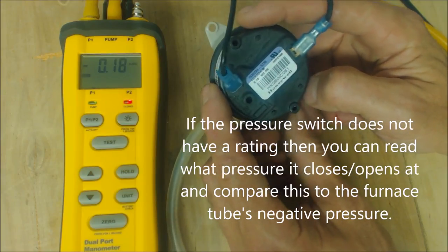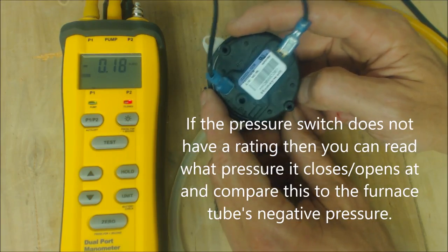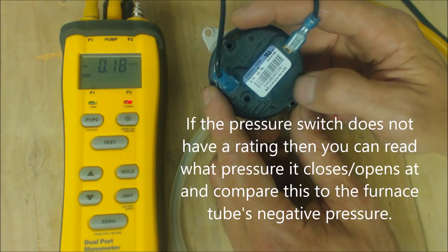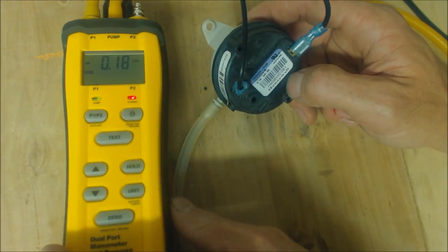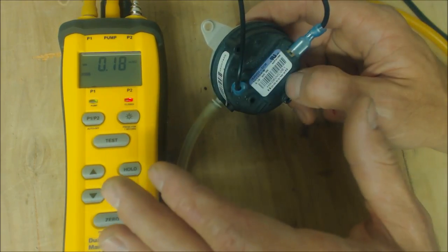I really do like this—it's not guesswork. It actually helps you confirm that you definitely have a bad pressure switch or a good pressure switch. It takes one thing out of play, especially if it's an intermittent problem. That's when I really like to use this with intermittent issues.